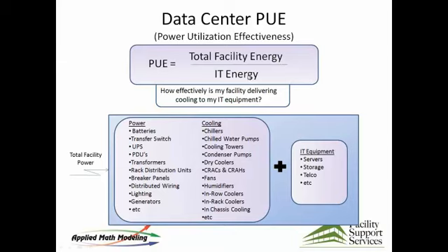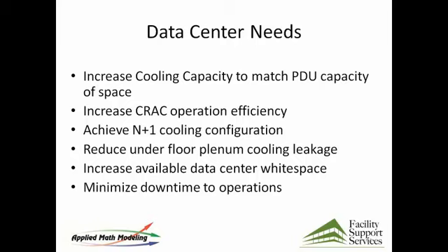I think the N+1 is a bit of a misnomer sometimes. Oftentimes people think they have N+1 because the total capacity of their CRACs when summed is greater than what they need for their IT load. But until you run a CFD and determine that, in fact, without any one of the CRACs, any given CRAC, and by the way, you have to shut them all down one at a time to see if it works. You never really know that you've got an N+1, do you? No, you don't. There are a lot of variables.